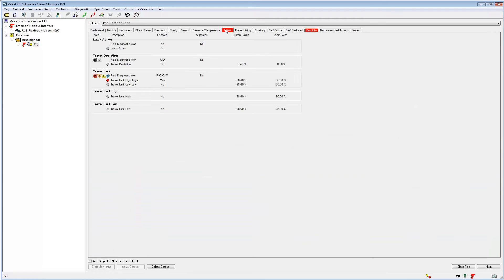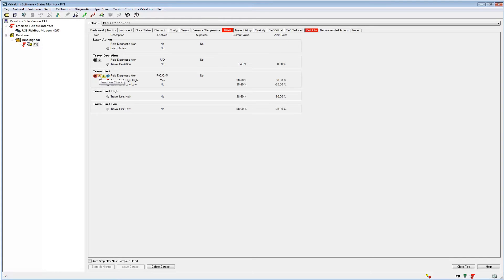Here we see the travel limit high high alert is active and we can see the field diagnostic categories for that alert such as failure, function check, out of specification, and maintenance required. The travel deviation alert above is not active, but we're still able to see what field diagnostic categories are assigned to this device.